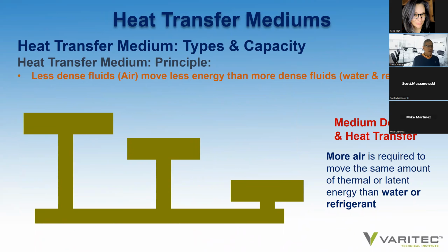Well, to understand high-performance HVAC, it's important that we understand the different properties of these three heat transfer mediums. Air is not a very dense heat transfer medium, and it can only carry 0.46 BTUs per pound of air. Consequently, to condition a building, you need to push a lot of air through the building to absorb the energy of that building effectively for it to be distributed outdoors. Well, if you have a lot of air, you need big ductworks in a building.